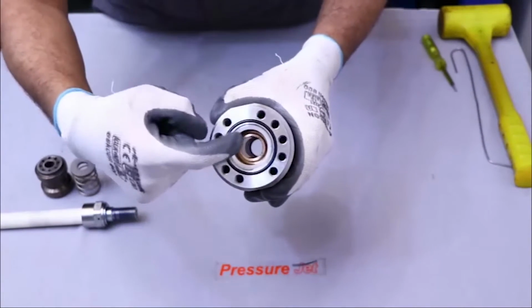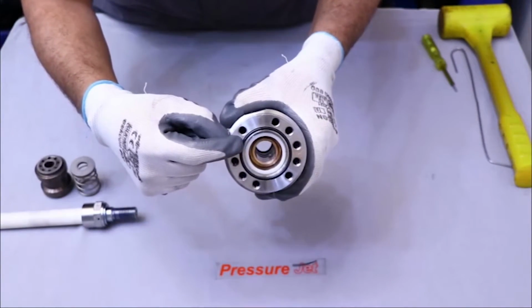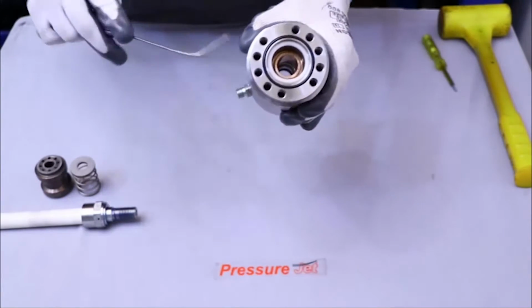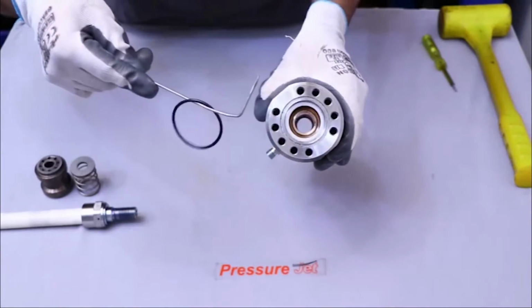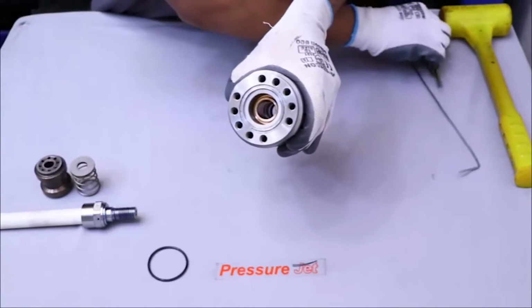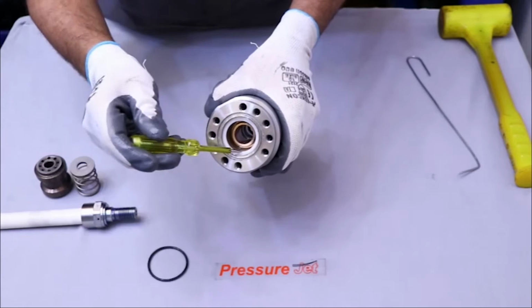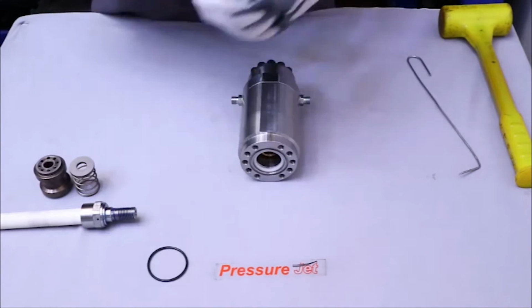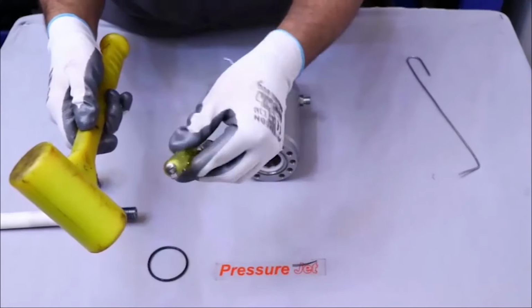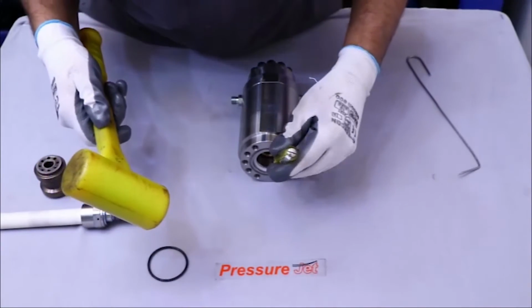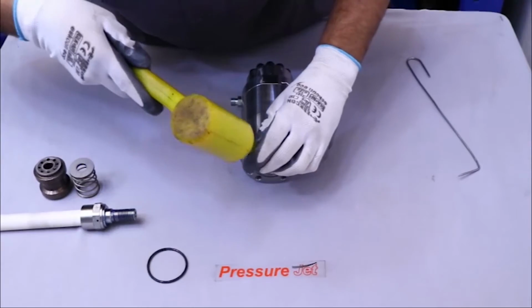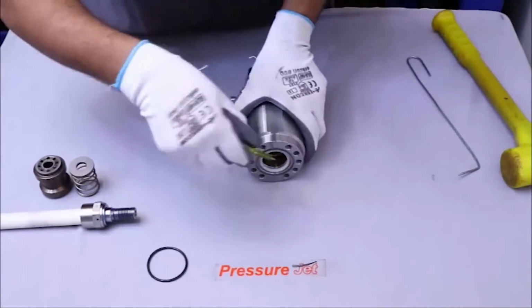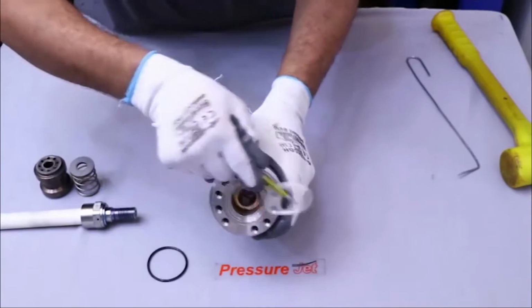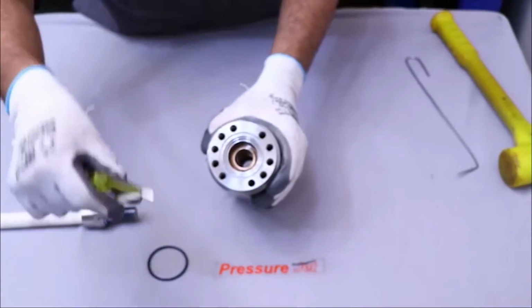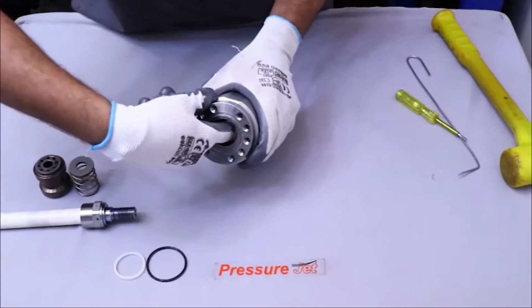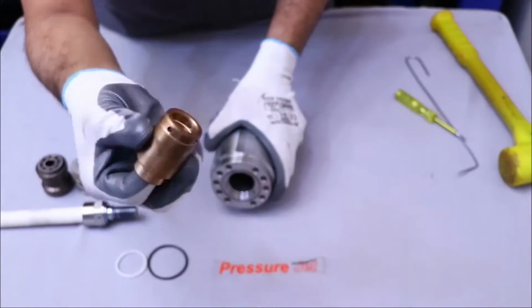This is O-ring and it is a pressure packing retaining ring. Take a pick and remove O-ring using that pick. This is a POM gasket. Use rubber hammer and screwdriver to take out POM gasket. After that, remove the pressure packing retaining ring manually.